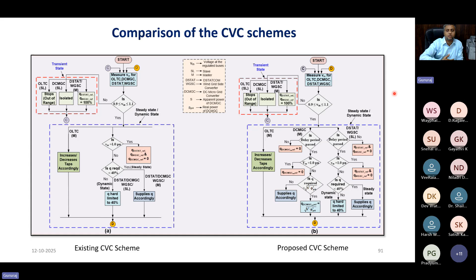To find a solution, we came up with a novel idea of introducing a delay before the operation of fast acting converters, such that the delay avoids the converters responding suddenly to any perturbation, allowing the OLTC to smoothly complete its action. Then, if necessary, these fast acting converters are allowed to inject reactive power. This is the whole ball game.